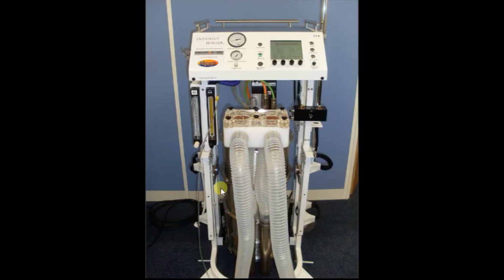Also on the Tafonius Junior, on this machine, you can see there are 2 areas here for some e-cylinders to be fitted. One on the right hand side here, one on the left hand side here. They can hold 1 oxygen e-cylinder here and 1 air e-cylinder here, or vice versa. You can see here on this machine I've got an option for an oxygen e-cylinder fitted here with the white tube coming down, the white hose, and oh yes, you can see it on here. There's a black hose coming down here to connect to the e-cylinder for an option for an air cylinder.